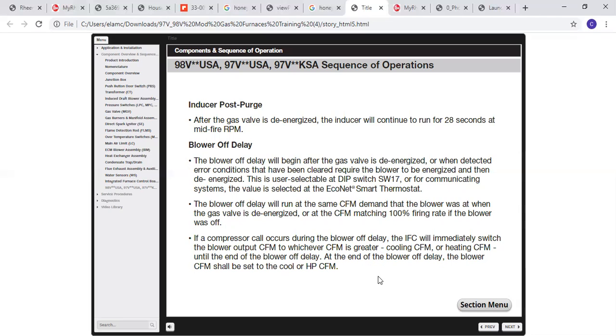The blower off delay will run at the same CFM demand that the blower was at when the gas valve was de-energized, or at the CFM matching 100% firing rate if the blower was off. If a compressor call occurs during the blower off delay, the IFC will immediately switch the blower output CFM to whichever CFM is greater, cooling CFM or heating CFM, until the end of the blower off delay period. At the end of the blower off delay, the blower CFM shall be set to cool or HP CFM setting.